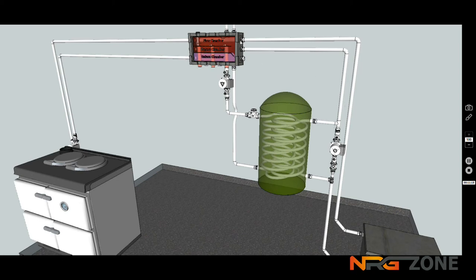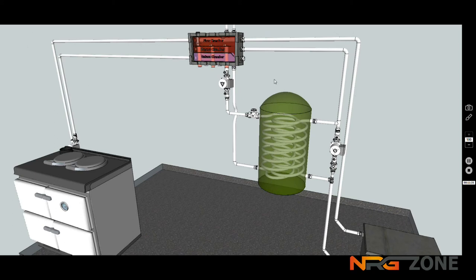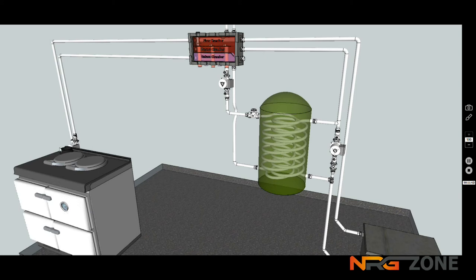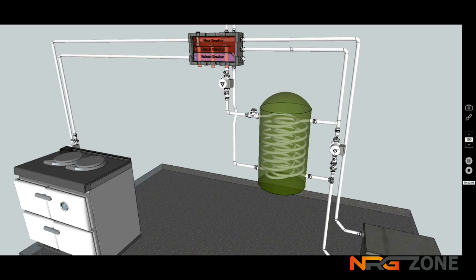And for that reason, it's critical that not just as the manifold is insulated so well, but that all of the primary pipework should be insulated, densely insulated, particularly at a high level. The better the insulation, the better the system is. A critical factor about insulation that people don't realize is, sometimes a person might calculate the amount of heat loss from pipework as just what might pass through the wall of the pipe. But it isn't. Because the water has to be reheated, the amount of fuel that's needed to get the water back up to that temperature, including the heat loss from the flue and the heating of the stove itself and all that metal, all adds to the huge amount of energy that's wasted because of not proper consideration putting it into the quality of workmanship or the quality of the insulation on the transmission pipework. It is ultimately one of the most energy effective decisions to make to spend time to insulate that pipework extremely well.